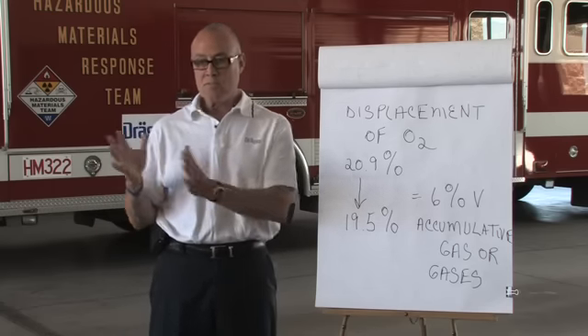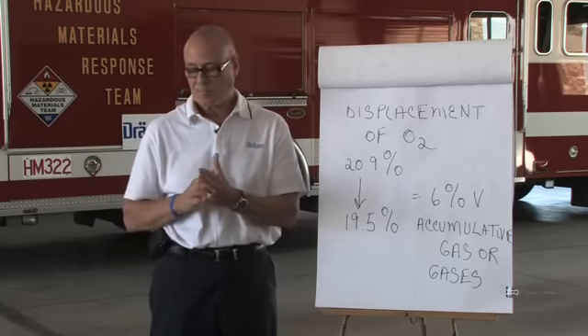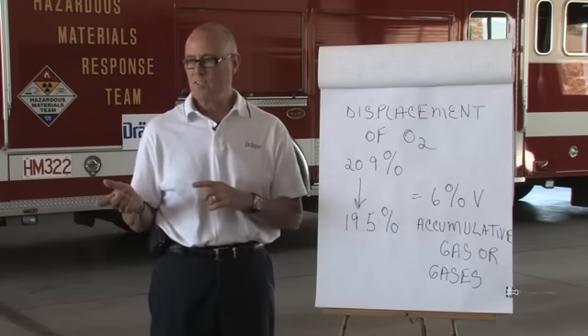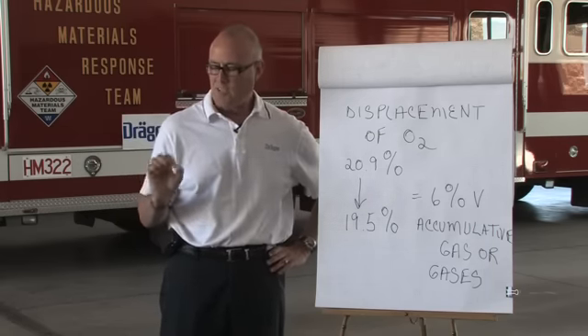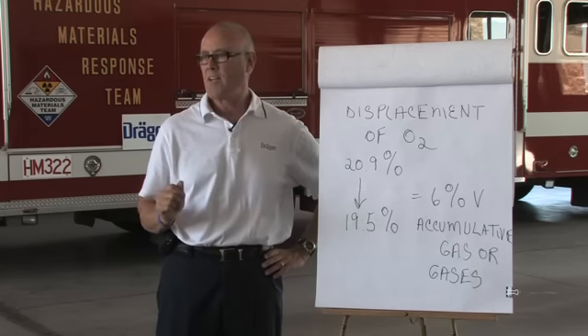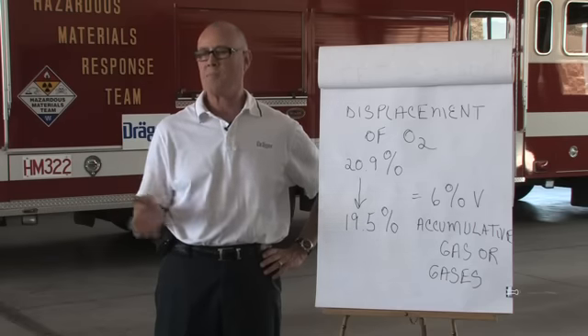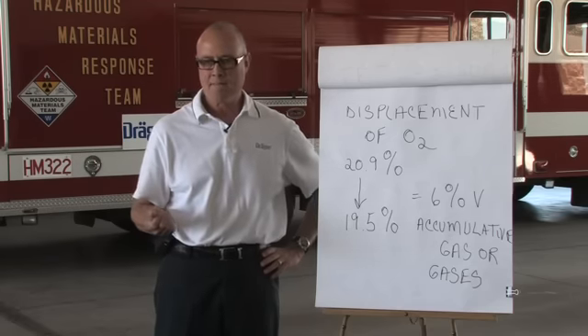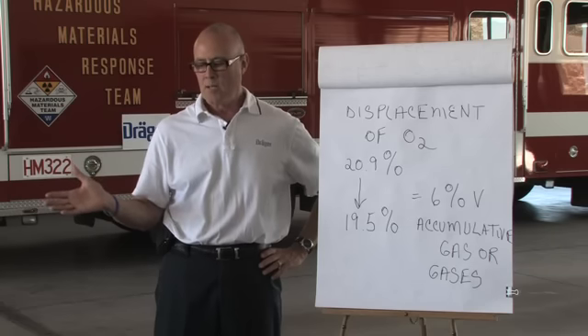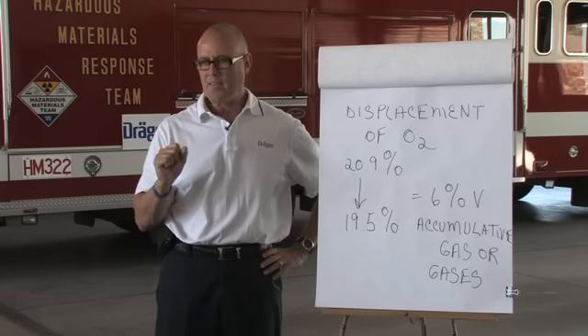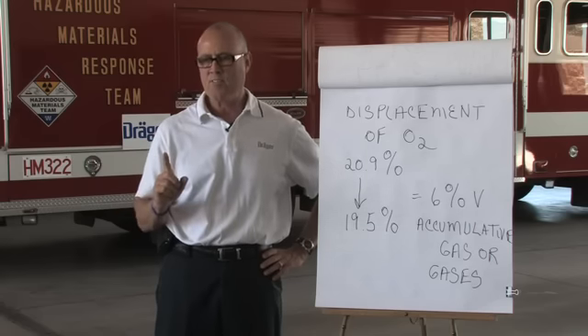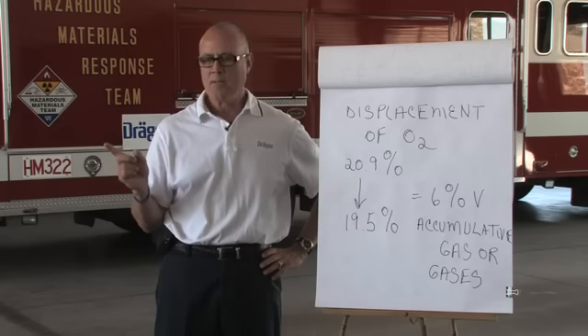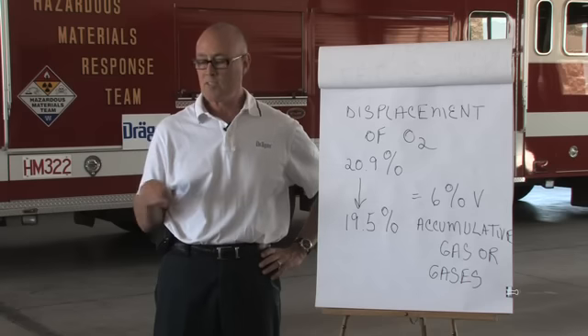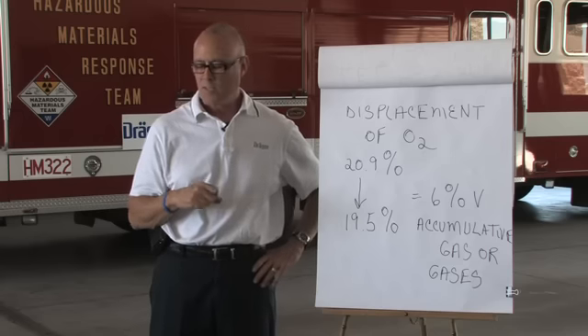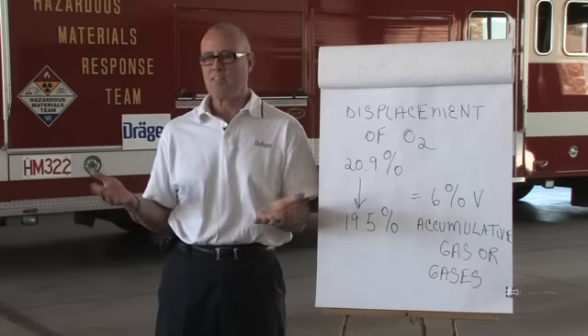Either the meter has drift, which Draeger meters don't generally drift, or you changed altitudes. Draeger instruments on startup never perform a fresh air calibration by themselves as part of their pre-entrance startup. Okay? There are some manufacturers that do, but I think we pointed that out at 74s, that Draeger does not do that, and they do it for safety, because if you're in an environment where you might have a gas around you and that does not have a warning property and you're unaware of it being there, but it's creating a movement on your meter, you don't want to start your meter up and have it fresh air itself in that suspect environment.